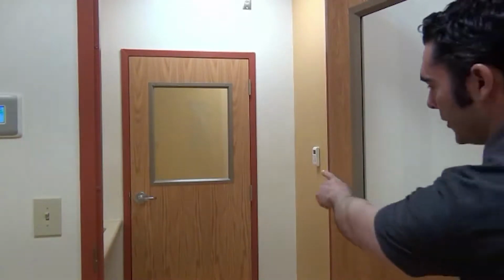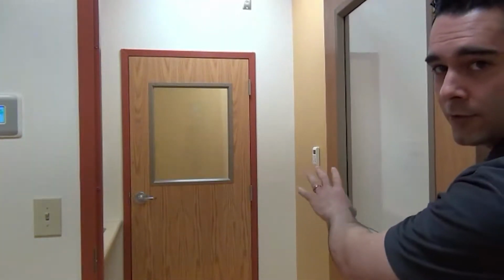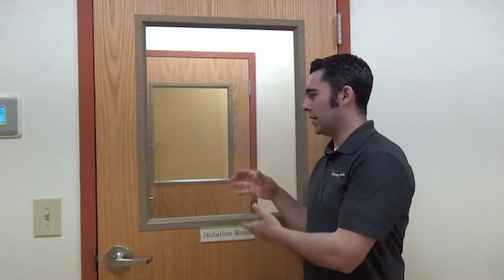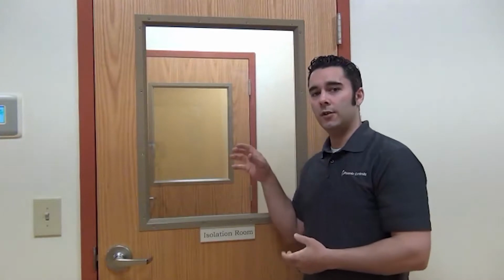Another healthcare application that Phoenix Controls products work very well in is isolation rooms and adjacent ante rooms. So what I have behind me is actually 2 rooms stacked on each other. This room in the back would be your isolation room, and this room in the middle would be your ante room. So this is going to effectively provide a barrier from the outside corridor and from the patient in the isolation room, so that you can have your wash down, wipe down inside the ante room, and then make sure that the patients are never contaminated. Now again, using a Phoenix Controls tracking pair for both of these spaces, we can guarantee the pressurization between the ante room and the patient room, and between the ante room and the corridor.